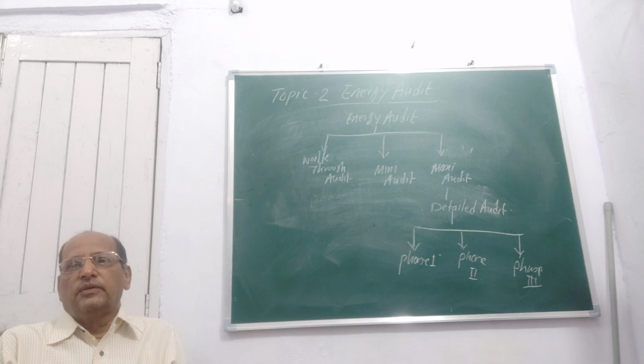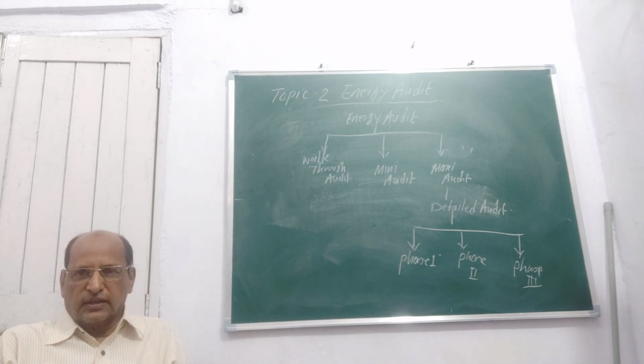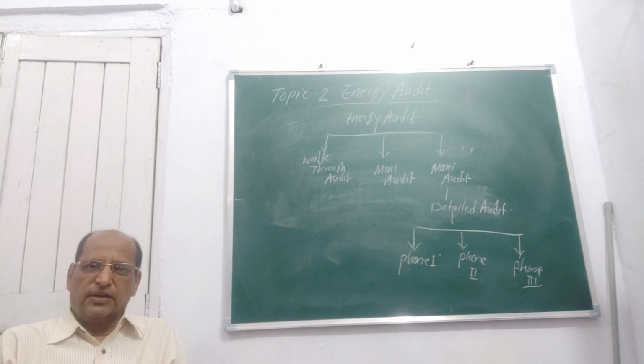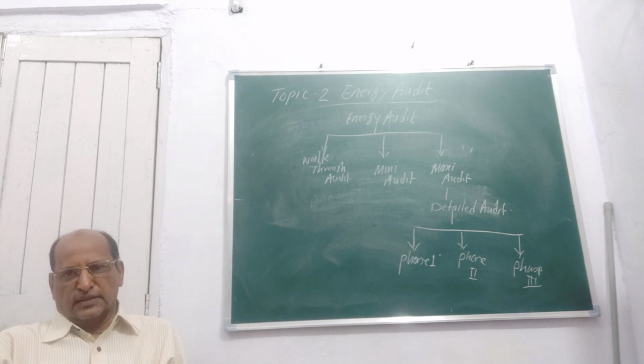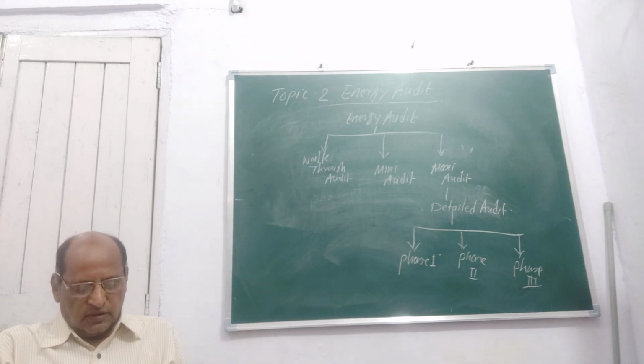That will give you the exact figure of whether the motor is running economically or uneconomically. If the standard values match the operating value, then it is economical running, and if the standard value is more and your operating value is less, then the machine is running under efficiency. So that will cause a loss of energy.